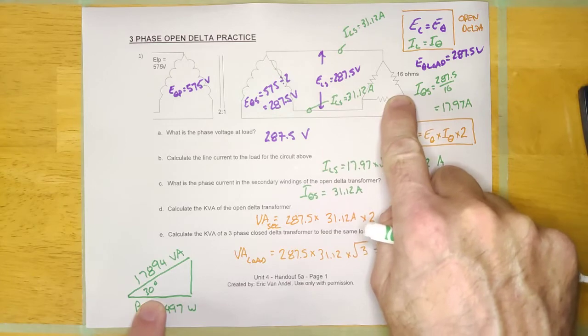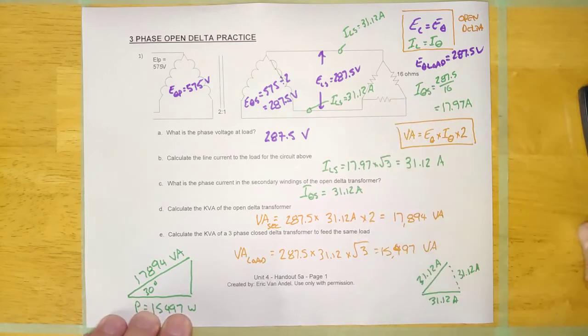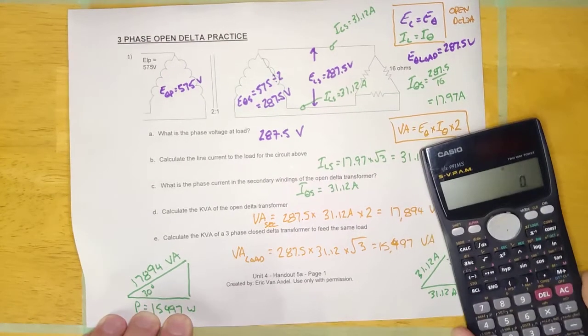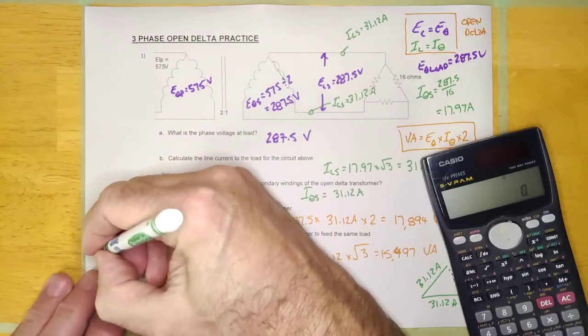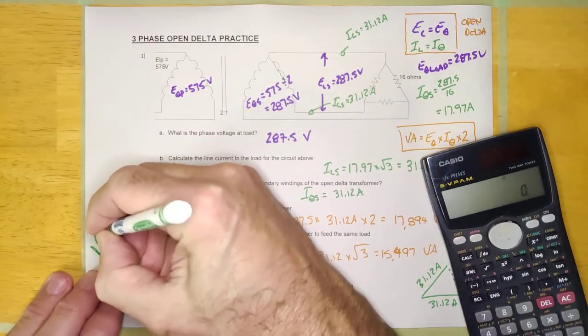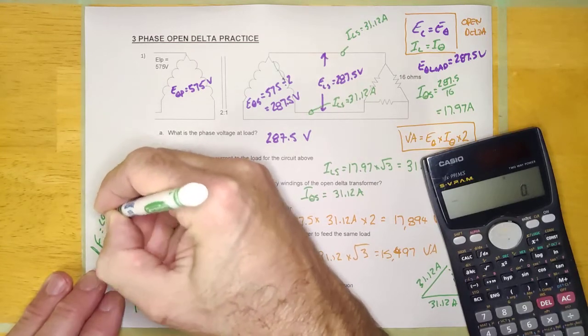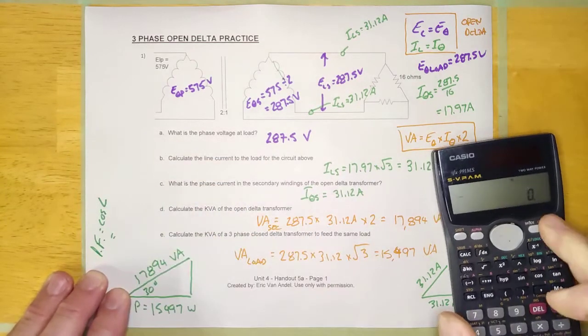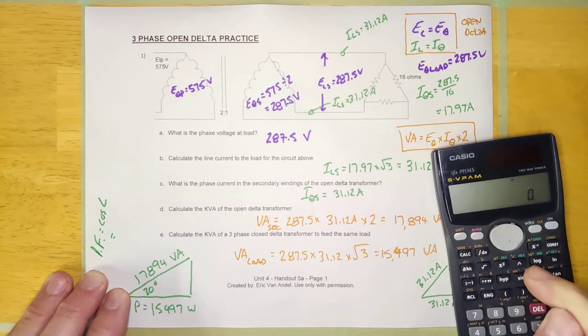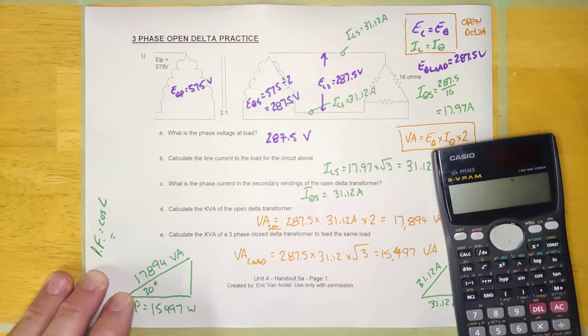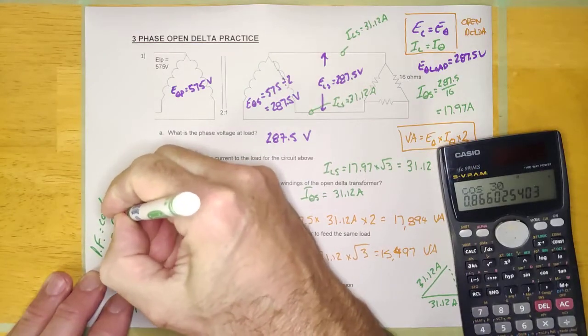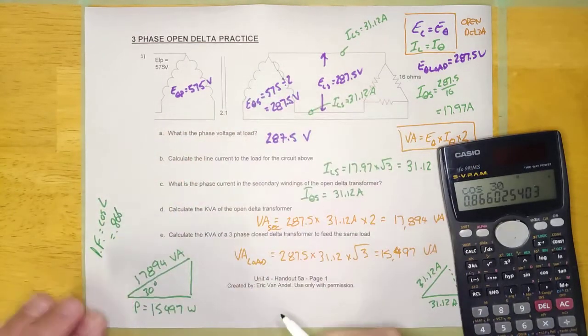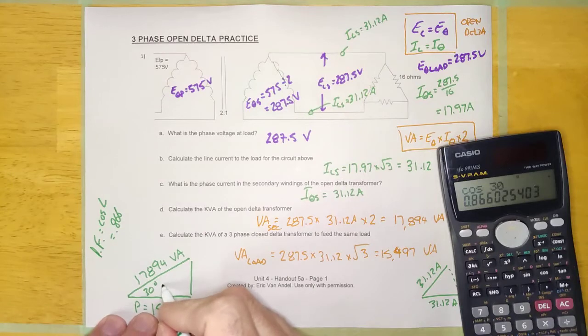And so this 17,894 VA transformer is running this 15,497 watt load at a power factor of whatever 30 degrees is, 0.866. All right guys, and if you don't believe me, let's do that here. Let's see what the power factor that transformer is running at. The power factor, it should be the cosine of the angle. And so if I hit cosine 30, it's 0.866.